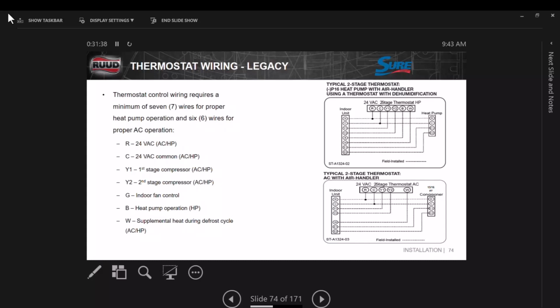Not going to communicate. And don't think that just because you ran brand new thermostat wire, that thermostat wire doesn't have a problem with that communication. It doesn't take much. You know how you can step on a piece of thermostat wire and you push the wires together? And it's just a barely touch. That's all it takes to kill that communication. Just a little bit. I've gotten involved with systems that have had thermostats changed, control board changed, and now they're saying nothing works. We want a new unit. And I said, did you change your thermostat wire? It's brand new wire. I said, change your thermostat wire.